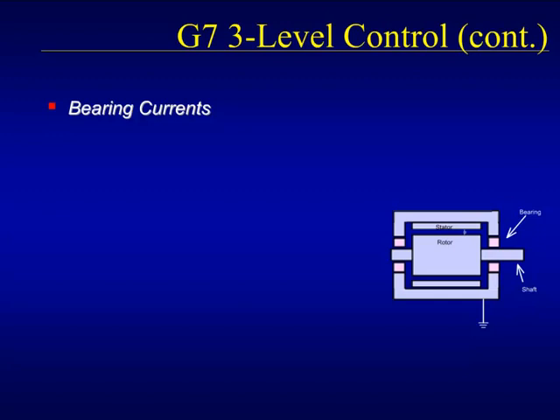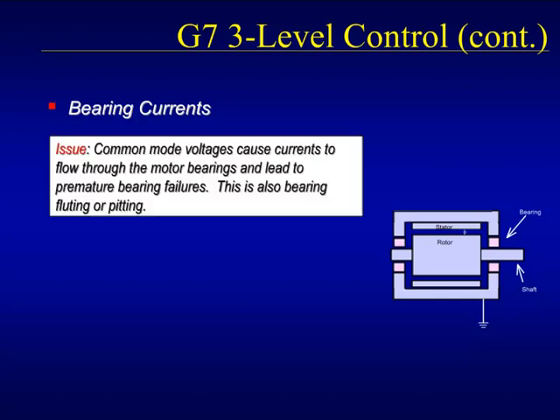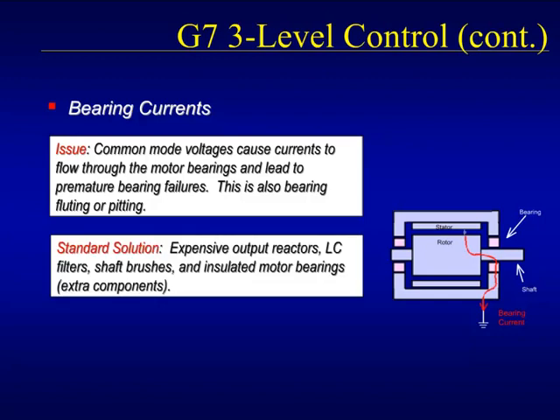Another solution to motor failures offered by the G7 is to the failure of motor bearings caused by bearing currents. Common mode voltages caused by capacitive coupling allow currents to flow from the rotor to the ground via the motor shell. This path takes the current through the motor bearings, which causes pitting and fluting of the bearing race, and also degrades the bearing lubrication.